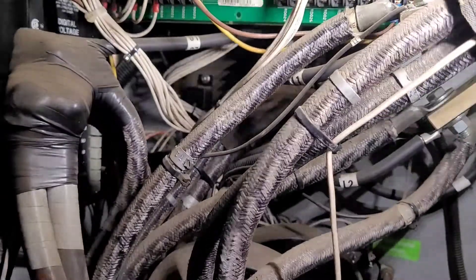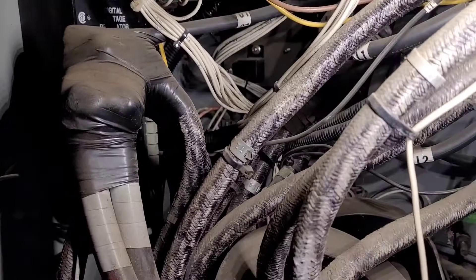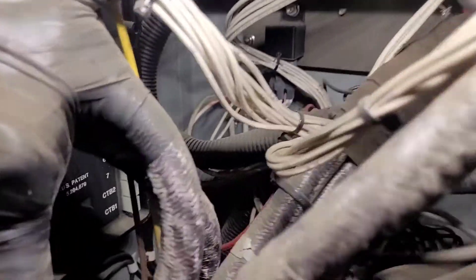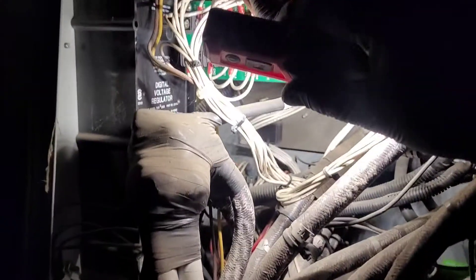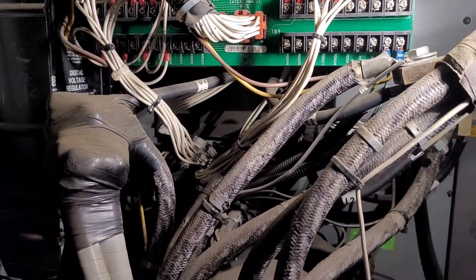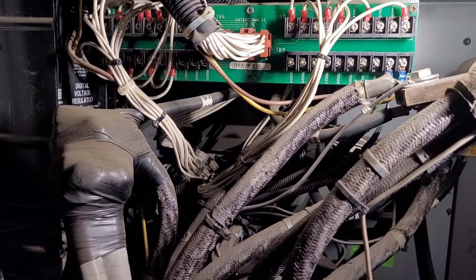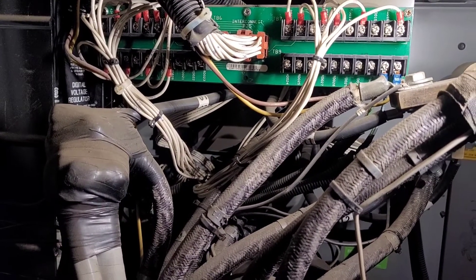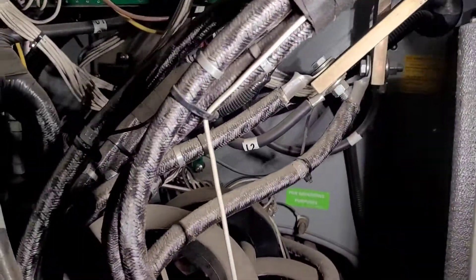Yeah, the fuses are back. So I just saw them, those fuses right there, back over yonder, those are the sensing fuses that come off the alternator. And those right there are what the controller reads for voltage sensing. And they're tied into right here. See? And that's where it gets its sensing from.